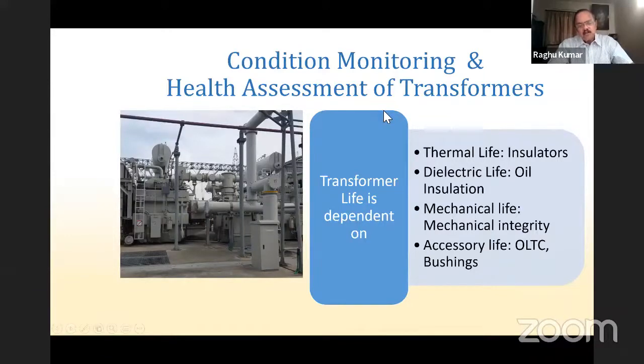The life of a transformer is dependent on thermal life, that is, the insulation. Thermal life is very important. Next is the dielectric life of the oil, then mechanical life, the mechanical integrity. After a few short circuits, the mechanical integrity needs to be checked, and accessories play a big role. The OLTC is the only moving part in a transformer, and then the bushings. Bushings are common failure points.